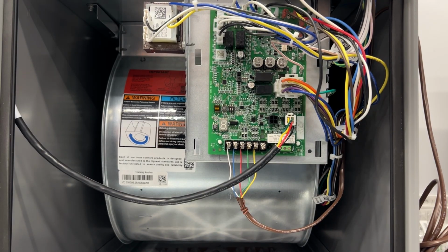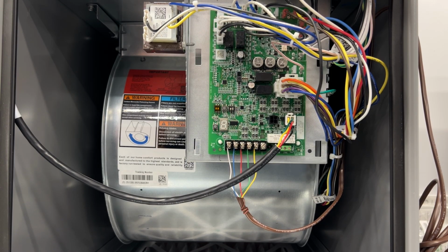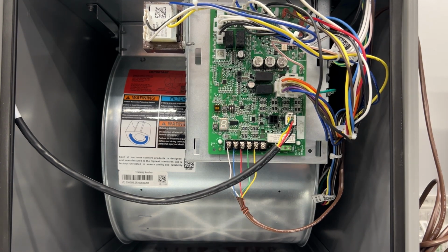So when you actually start this thing up, you'll notice that it'll go through a little code feature here, and then it's going to go into a fan purge. It's going to purge the system for 5 minutes. Now, obviously, I'm not going to stand here for 5 minutes, but you'll have that fan running for 5 minutes, and then you have about a 90-second delay, and then the unit will go into normal operation. But as soon as you let that power switch go, it will have to go through that cycle again.